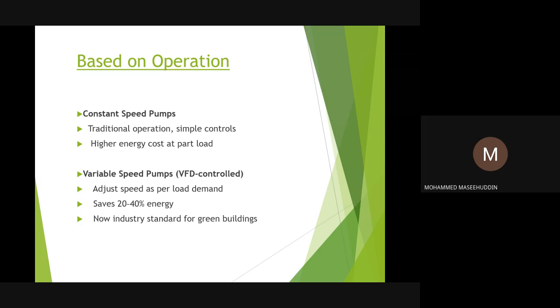So now if there is no demand, there is no load required by the chiller, and the chiller needs less water, then we can run the pump starting from, say, 20%, varying it up to 100%. So 20, 60, 50, 40, 80, whatever the demand is as per the chiller, we can vary it. And with this kind of pumps, we can save a lot of power as well, because when there is less requirement of load, obviously we can run it on less speed or less frequency, which will consume less power. So the power consumption can also be very good here. Whereas in the primary circuit pumps, which are constant speed pumps, even if the load required is less or more, it runs on constant speed and takes the complete power, and the power consumption in that case will be higher than when the pump is running on variable speed.